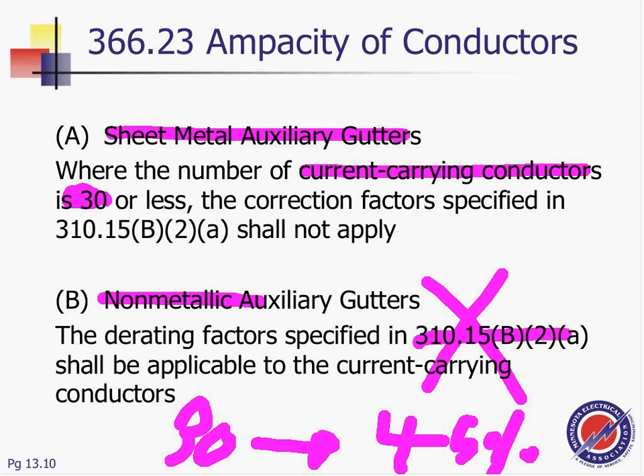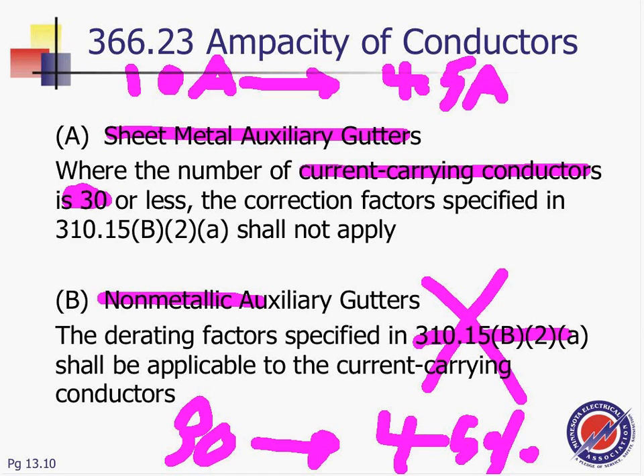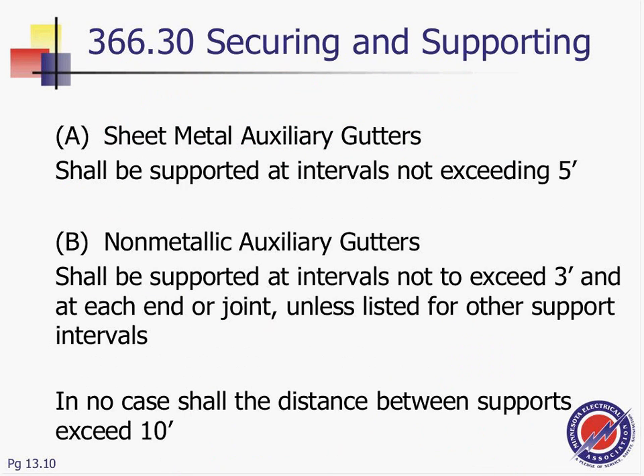What does that mean? If I have a 10 amp conductor, just for the heck of it, I have only 4.5 amps I can use. So a conductor that's rated for 10 amps, I'm just throwing this out, I can use 4.5 amps of it, less than 5 amps. Well, you just threw a lot of copper in the ground. You can't use it. So if it's metallic, no problem, 30, and you still kick it. So that's basically it.